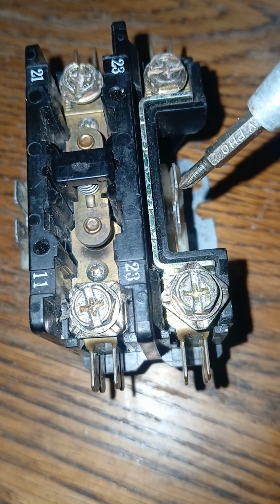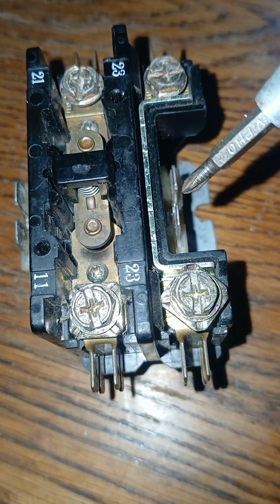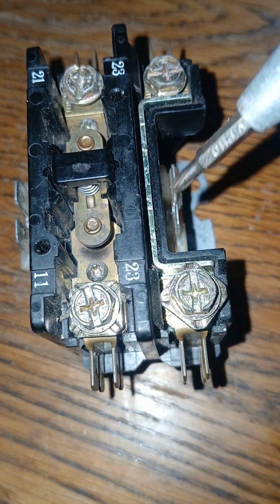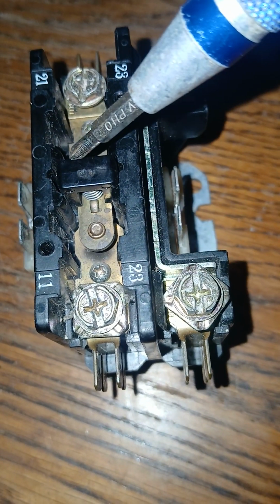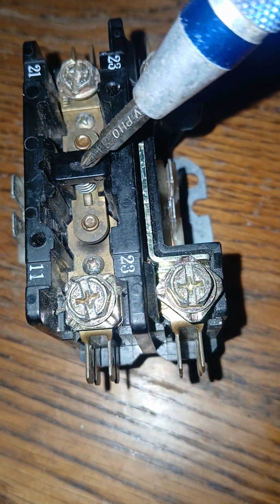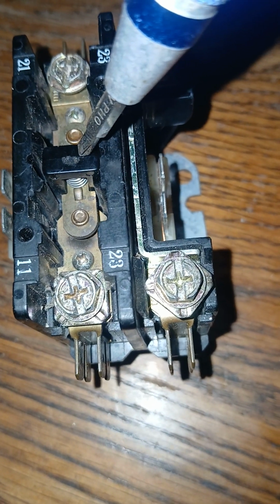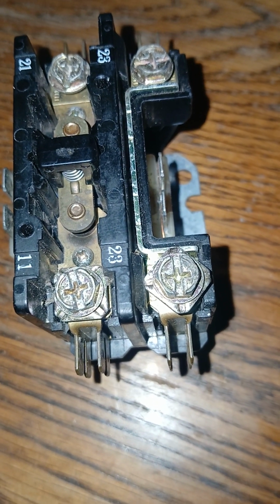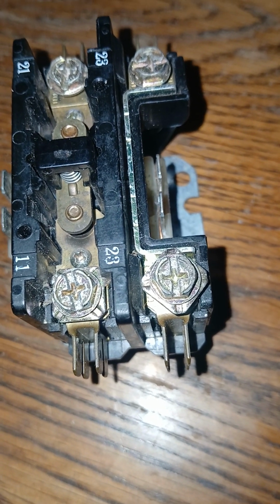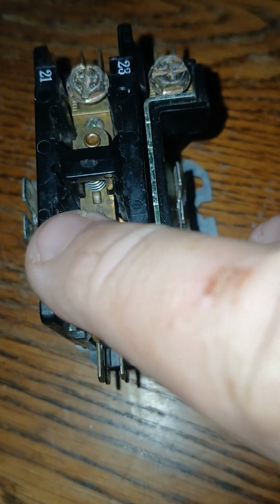So if this were a light switch, we would have to go over here and flip a light. But this actually, when the thermostat calls for, say, cooling, hypothetically, it energizes this 24-volt coil, or plus or minus, and then it pulls this in. Now one caveat to keep in mind: if this thing gets pulled in at all times, if you go out to your outside condenser unit, and the compressor and the fan is just incessantly running without stopping, eventually it could burn it up. So this could be a safety device too.